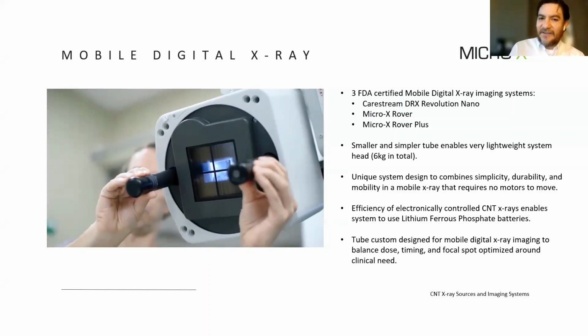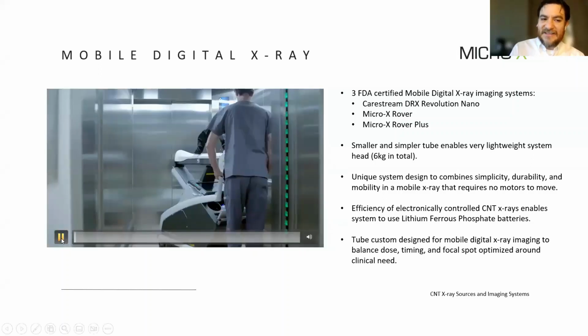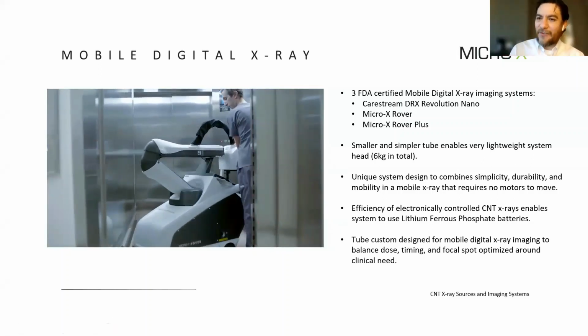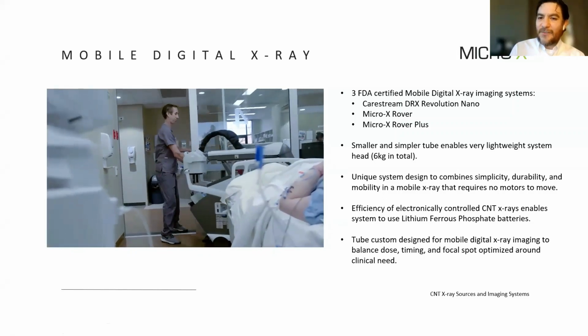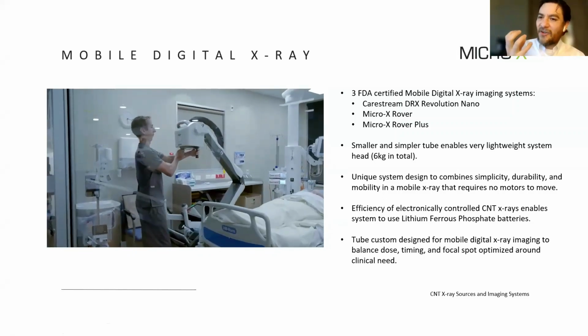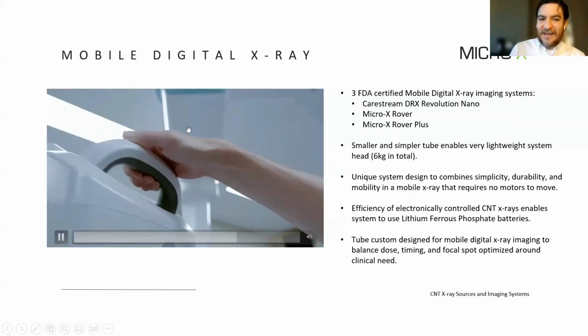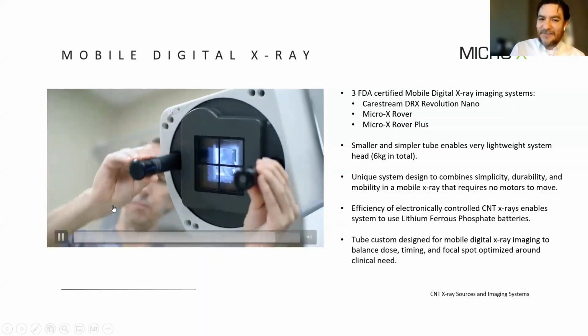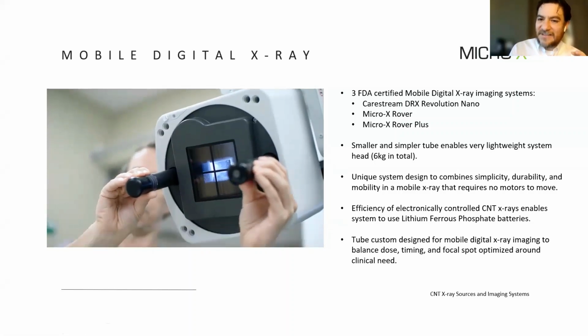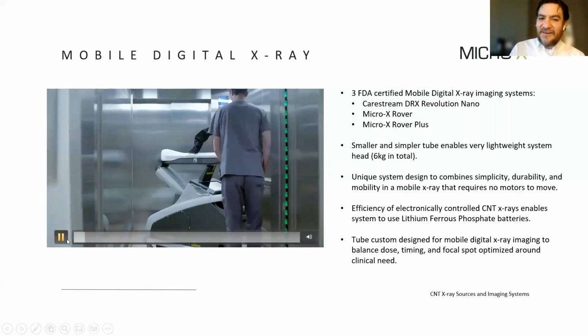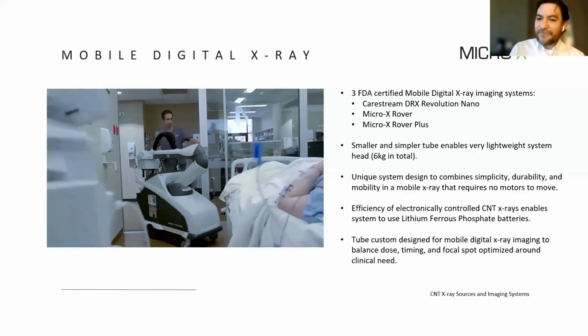We now have the Micro-X Rover and the Micro-X Rover Plus. The Rover Plus has the higher power X-ray tube in it. And really what we've done is use that smaller, simpler X-ray tube to create a head that is only 6 kilograms in total, and that allows us to have a very flexible system. So it allowed us to engineer a system that was simpler and easier to use, more reliable, and didn't require any motors to move, but is still very simple and very easy to maneuver.